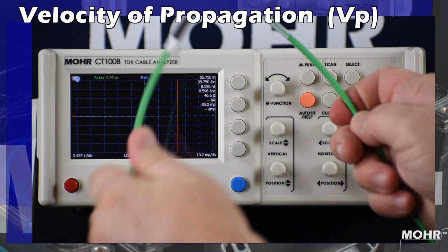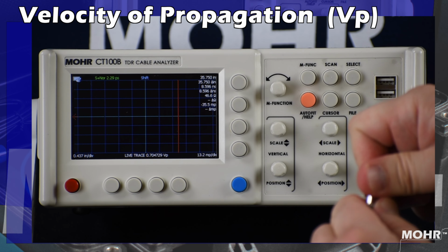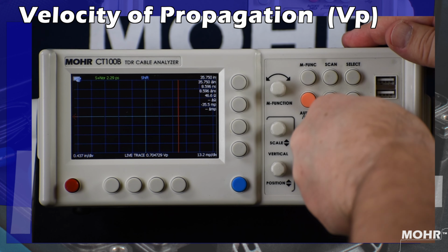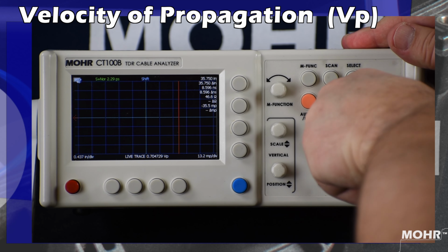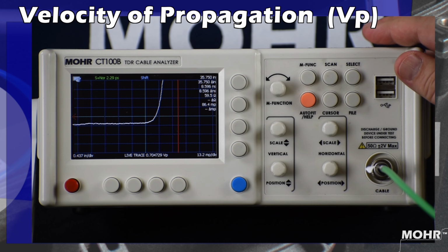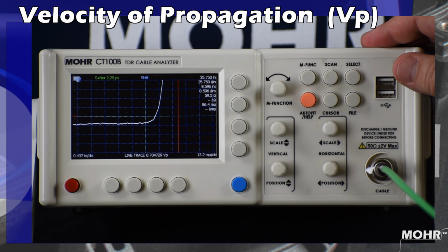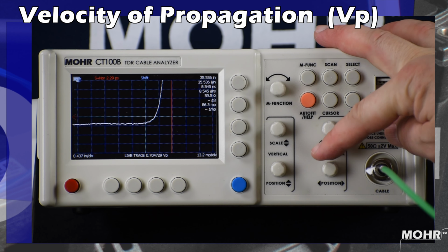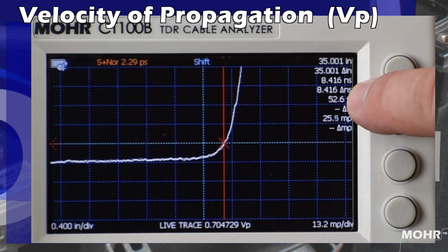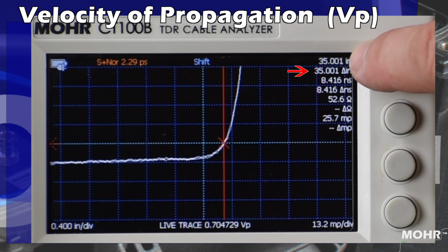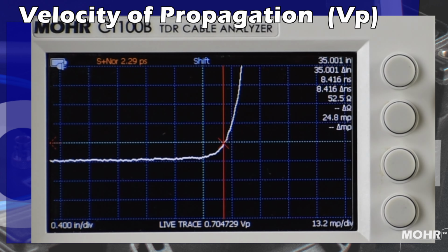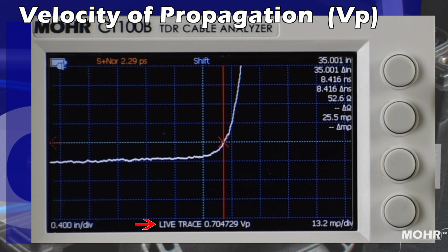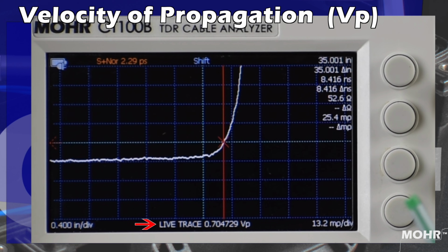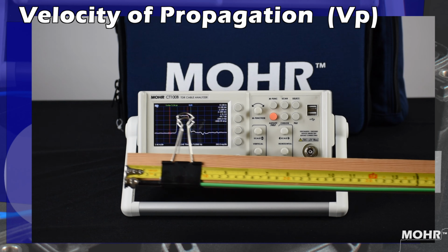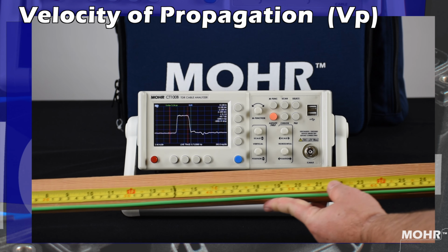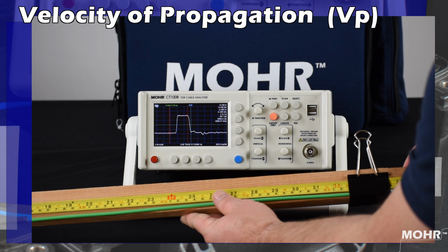Now to put it into action by measuring another cable, try this shorter cable and see what it measures. Place the second cursor at the end of the new cable, and we can see our cable length of 35 inches right here. And it's based on the VP of 0.704729 that we determined here. And we can verify our physical measurement of 35 inches with our tape measure.